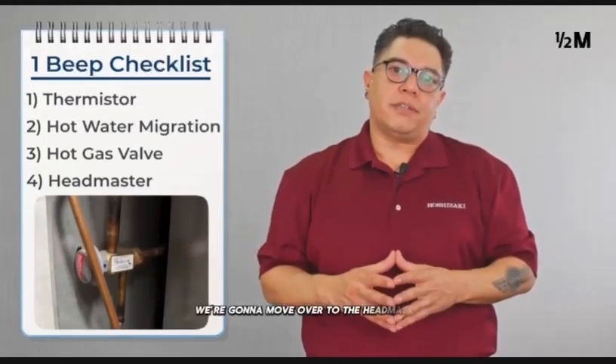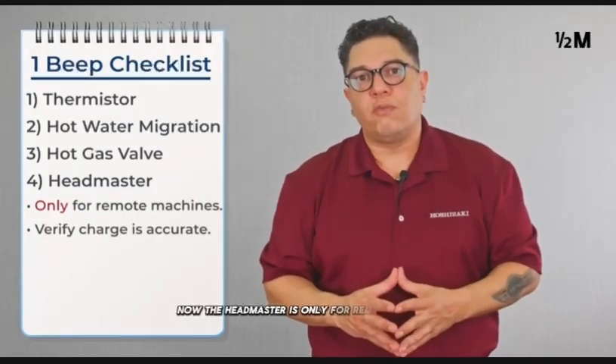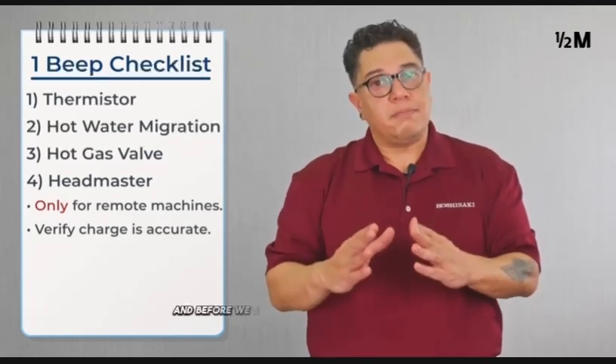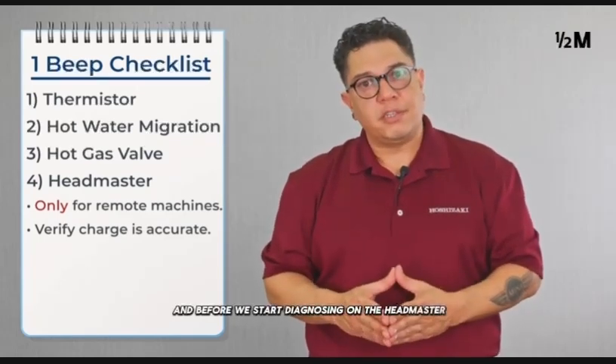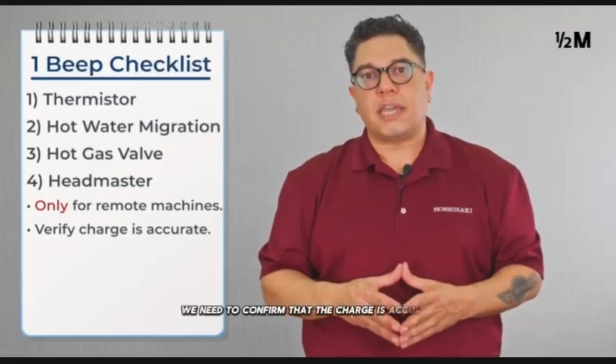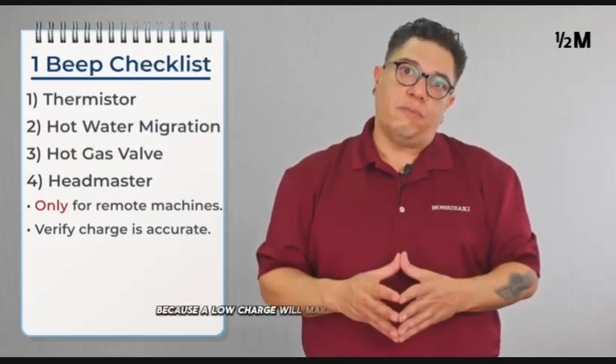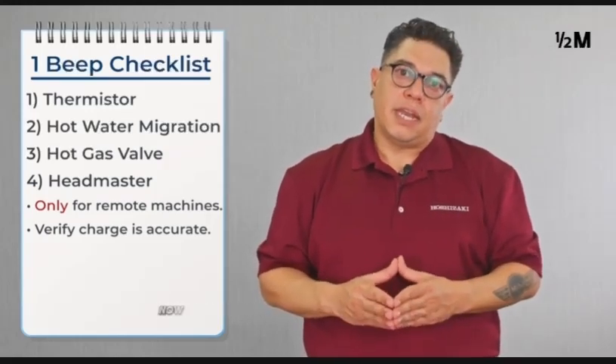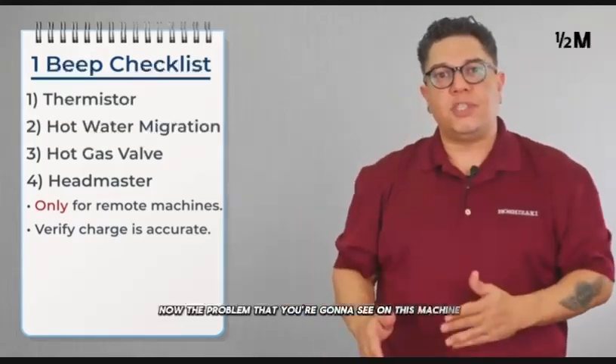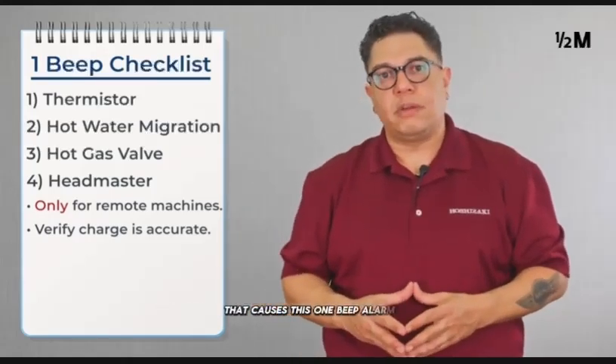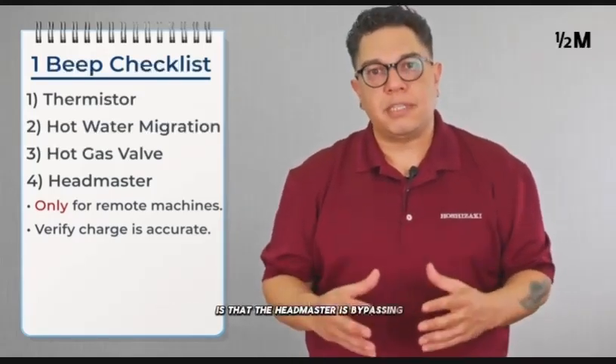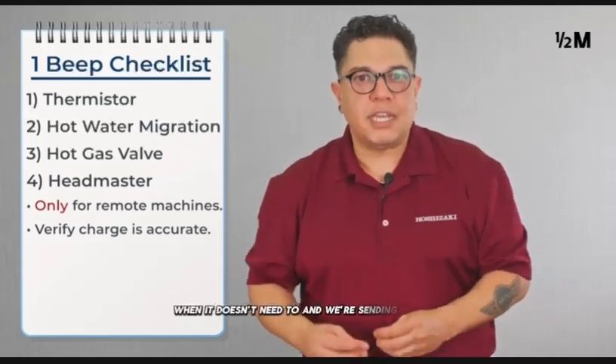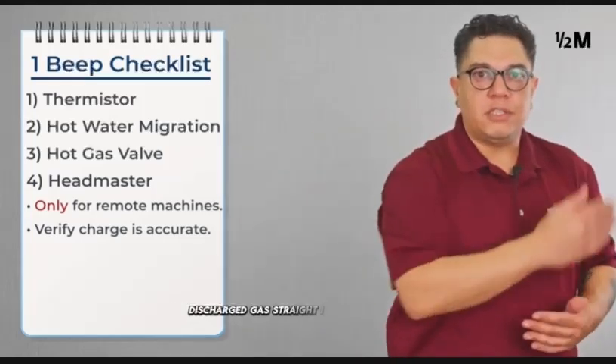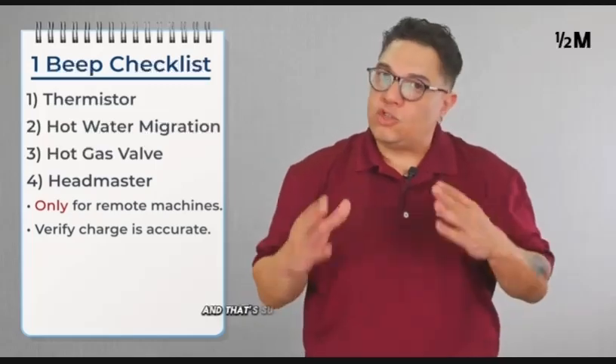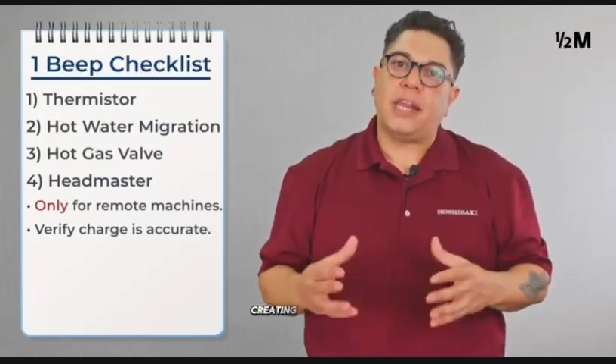After we check the hot gas valve, we're going to move over to the headmaster. Now, the headmaster is only for remote machines. And before we start diagnosing on the headmaster, we need to confirm that the charge is accurate because a low charge will make that headmaster bypass. Now, the problem that you're going to see on this machine that causes this 1 beep alarm is that the headmaster is bypassing when it doesn't need to, and we're sending all that discharge gas straight into the evaporator. And that's superheating the evaporator, creating this 1 beep.